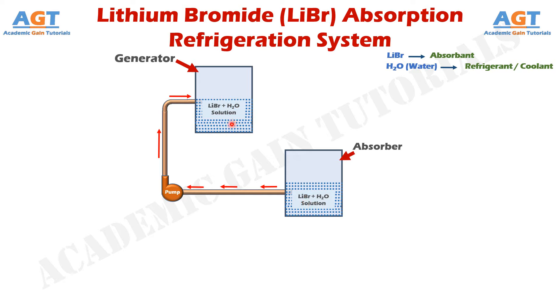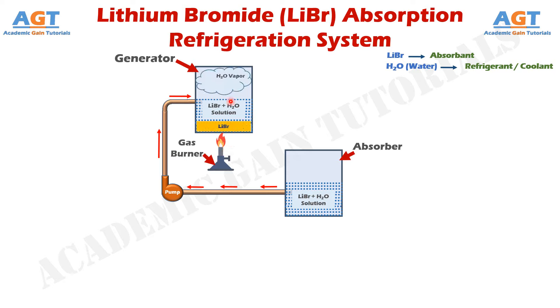When the solution of lithium bromide and water reaches the generator, here we have a gas burner. Using this gas burner, we provide flame and heat to this solution inside the generator. The function of the gas burner is to provide heat to the generator, and when heat is applied to this solution, water is converted to vapor. When water from this solution turns into vapor, only lithium bromide is left in the generator. Then the generator sends this lithium bromide back to the absorber through this connecting pipe.